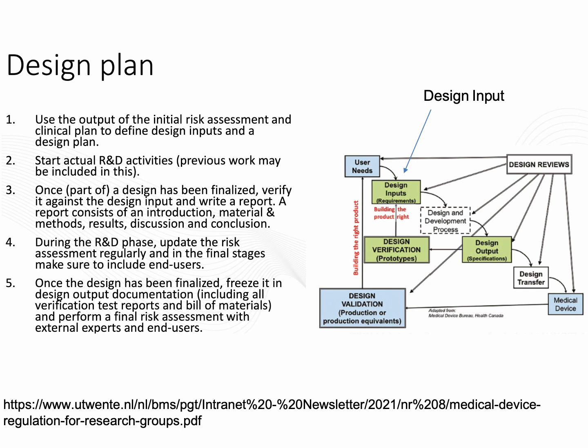Now, let's go back to the design plan and the big picture, because in the next slides I'm going to talk about the design input only. So we looked into, again, the big picture where we have the user needs, we have the design input and requirements, and we have a design process and design output. Then we have a verification, it's a type of iteration. Then we are going to transfer the design, getting the medical device, and then we are going to validate the design based on the user needs. Now let's go over the design input requirements.